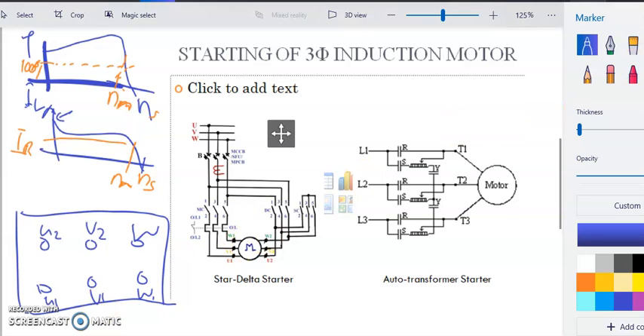But some motors are labeled as U1, V1, W1, then here are U2, V2, and W2. What is underneath the terminal connection? This is the connection between the coils. The incoming source goes into the coils inside your stator, then comes up at U2. Then V1 goes into the circuit and comes up at V2. The same for W1 here, it goes into the coil and rises at W2.